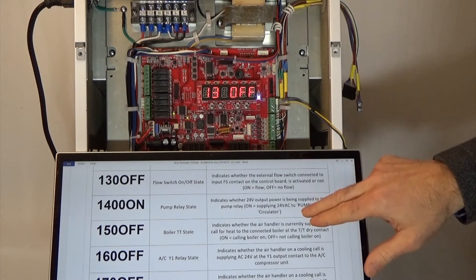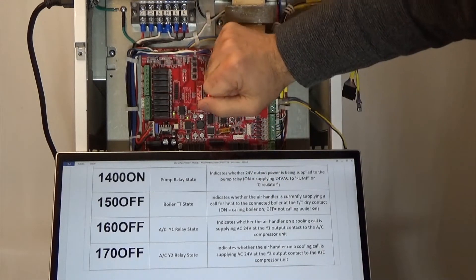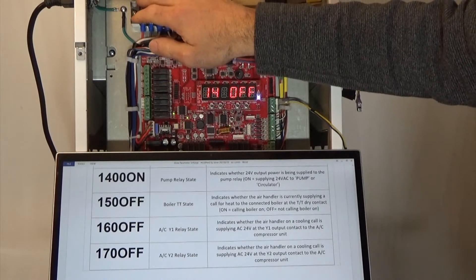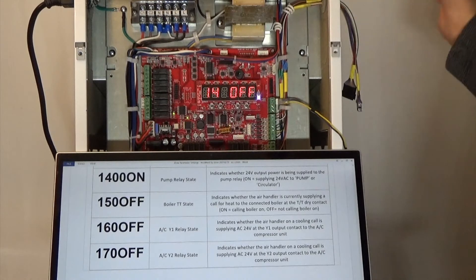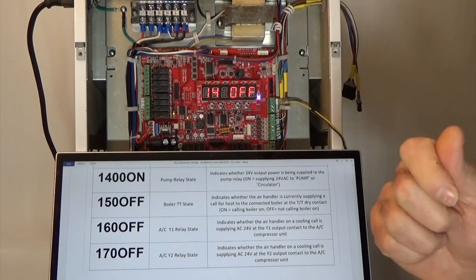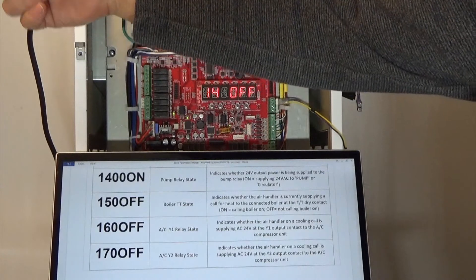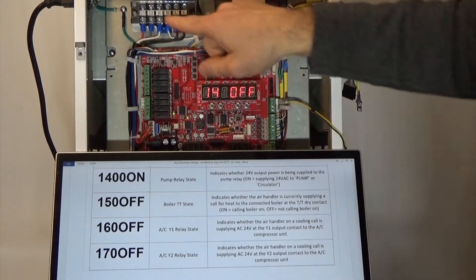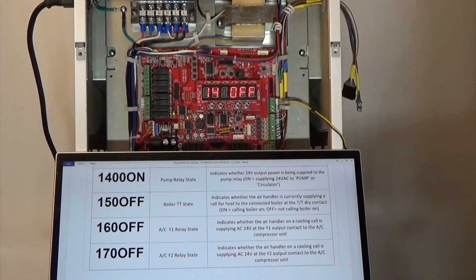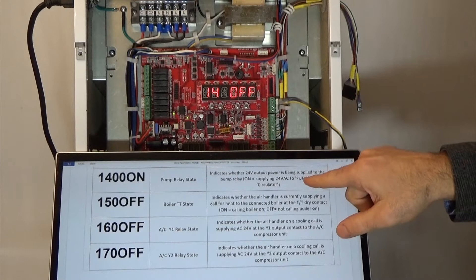Parameter 14 gives us the pump relay state. We have a 24-volt pump connection on the unit — this is different from the main variable speed pump controller. The variable speed control is controlling the pump supplying water to the iFlow. This 24-volt output, marked circulator, would be used if you need to bring on a primary loop pump — you would need a relay to 120V to bring on the primary loop pump, while we directly control the secondary loop variable speed pump from the C1 and N connection on the unit. Parameter 14 tells us whether we're supplying 24 volts to that circulator contact.